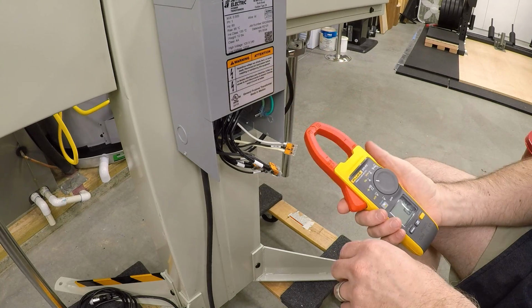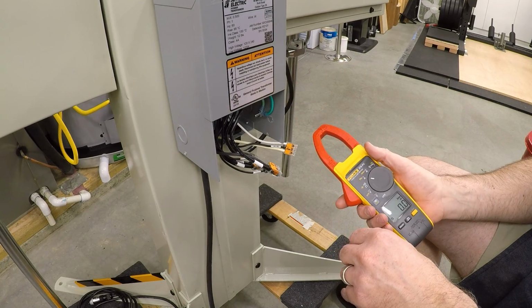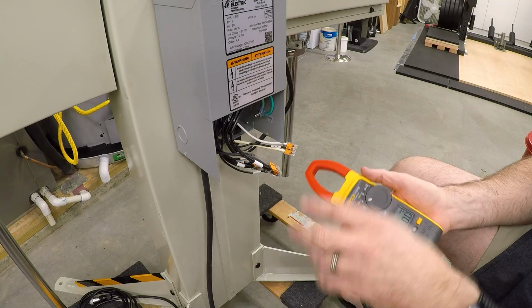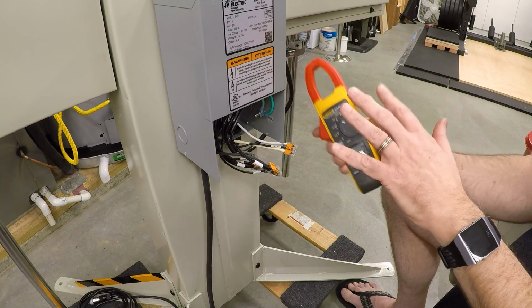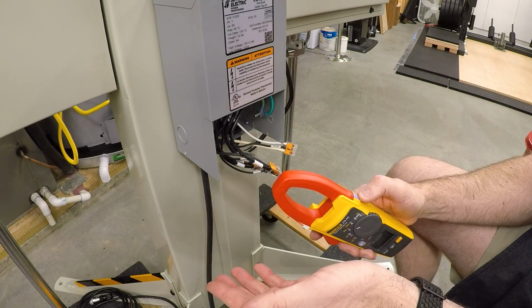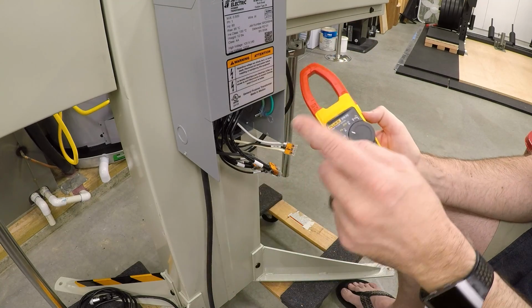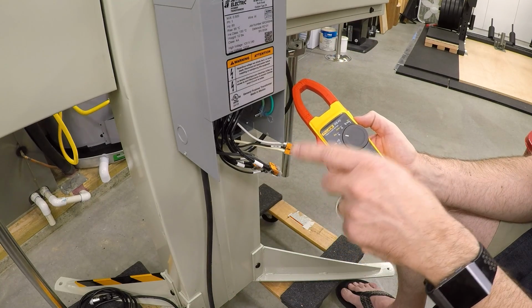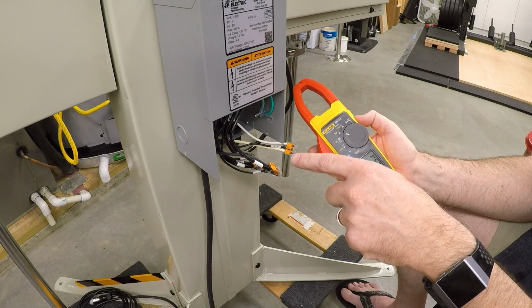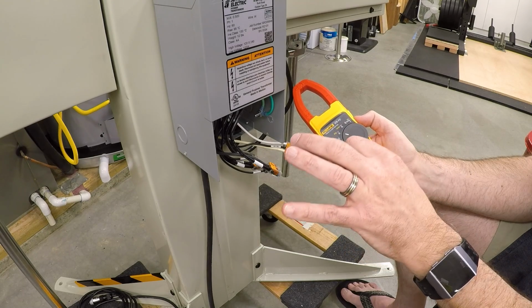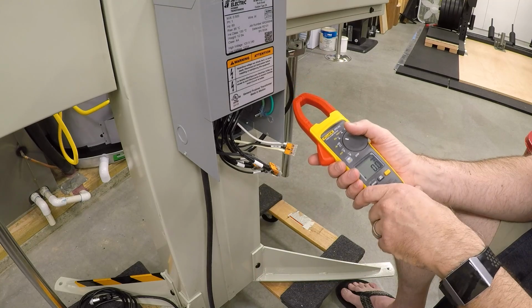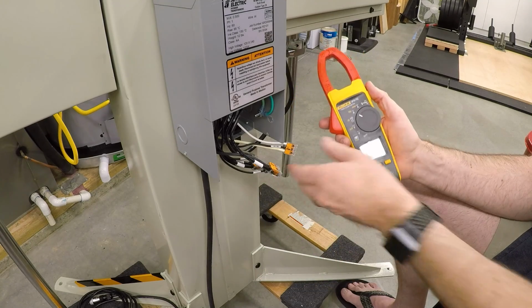So let's take some measurements here just for fun and see if what I said is actually true. The current in the secondary, the output at lower voltage, should be higher than the current drawn from the input. We should also see a lot of current in the low voltage secondary coils and almost none in the high voltage primary coils. Let's see if that's really true.